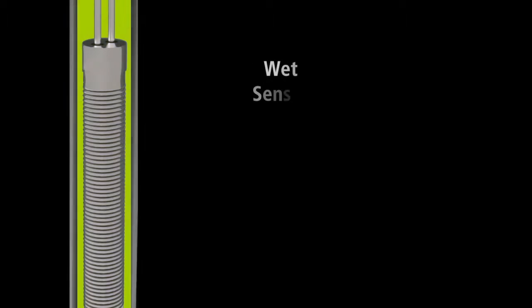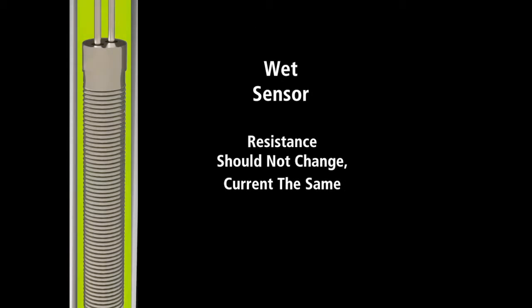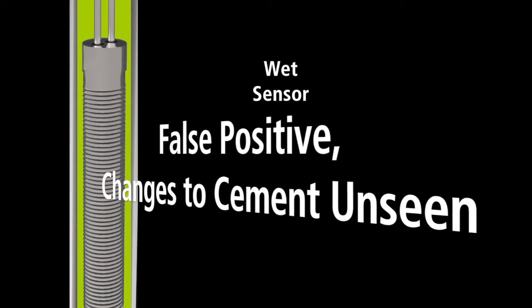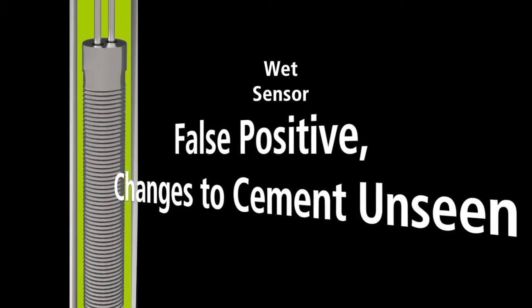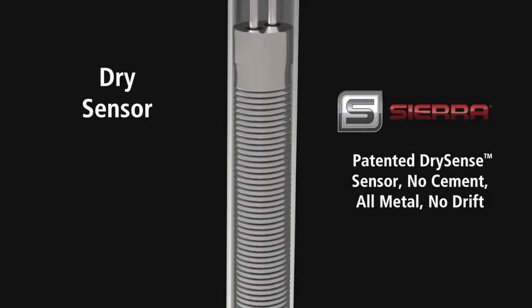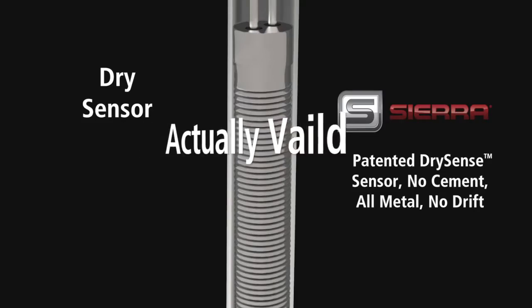The resistance of the platinum wire shouldn't change, and the current running through the sensor might be the same, both of which would validate OK. This is a false positive, as the drift inherent in a wet sensor design would remain unseen. Sierra's DrySense all-metal no-drift sensor has a big advantage during in situ calibration validation. With Sierra's all-metal DrySense velocity sensor, you have the mechanical design confidence that there will be no drift and that in situ calibration validation is indeed actually valid.